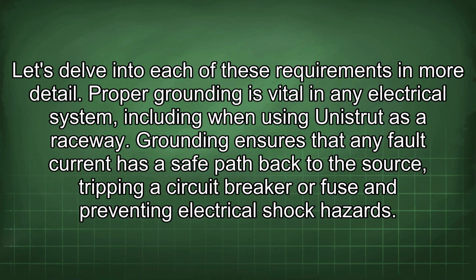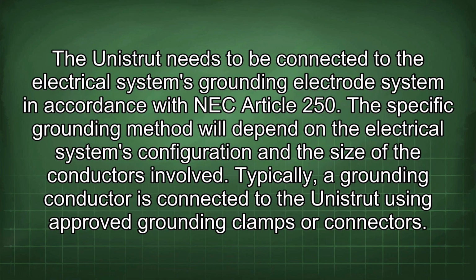Proper grounding is vital in any electrical system, including when using Unistrut as a raceway. Grounding ensures that any fault current has a safe path back to the source, tripping a circuit breaker or fuse and preventing electrical shock hazards. The Unistrut needs to be connected to the electrical system's grounding electrode system in accordance with NEC Article 250. The specific grounding method will depend on the electrical system's configuration and the size of the conductors involved. Typically, a grounding conductor is connected to the Unistrut using approved grounding clamps or connectors.